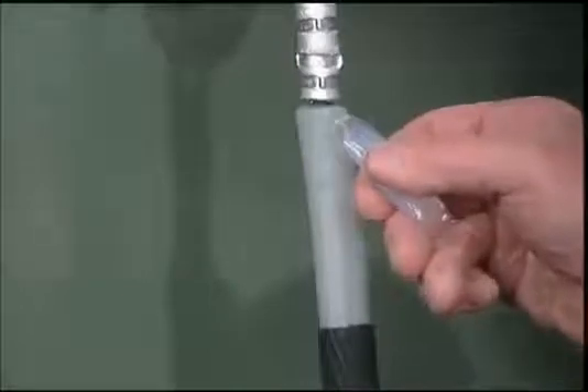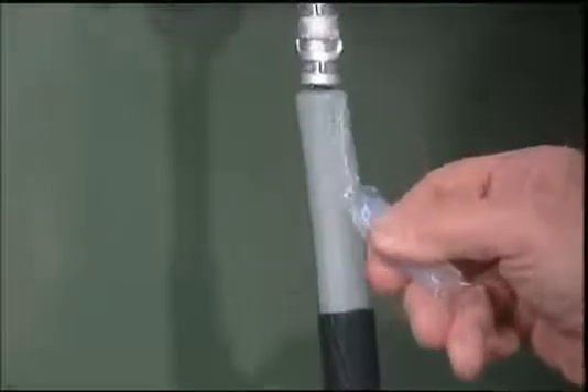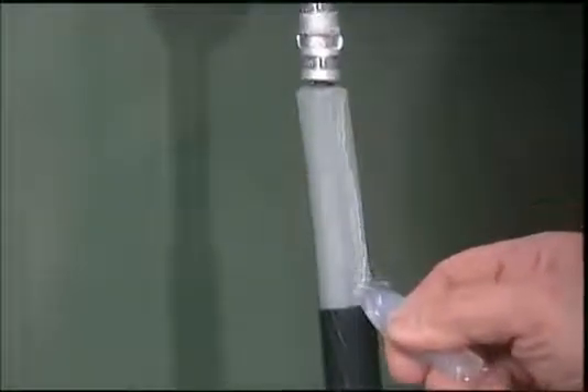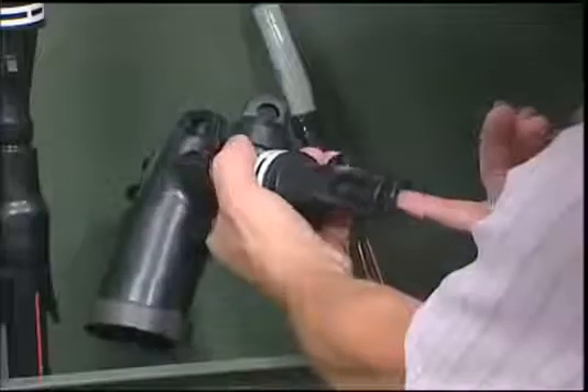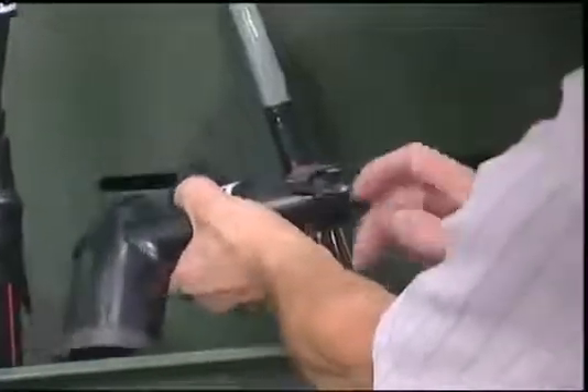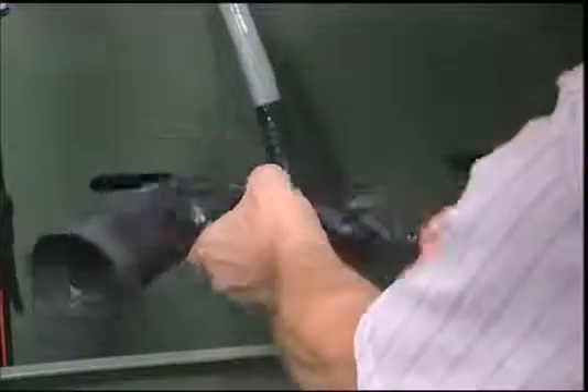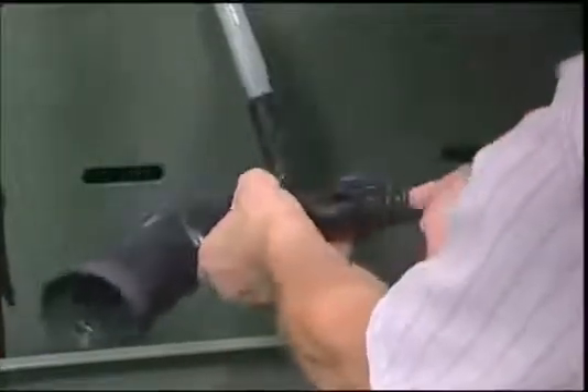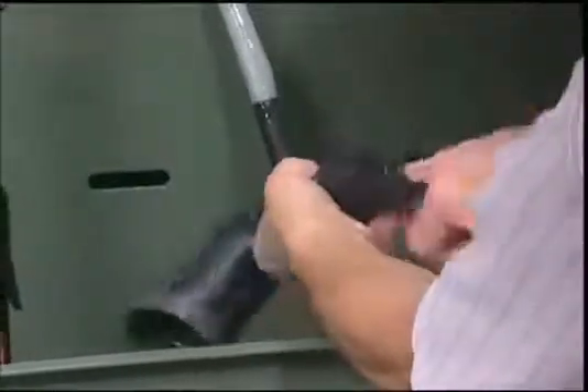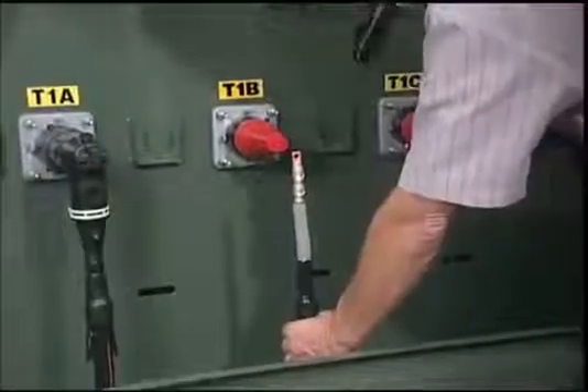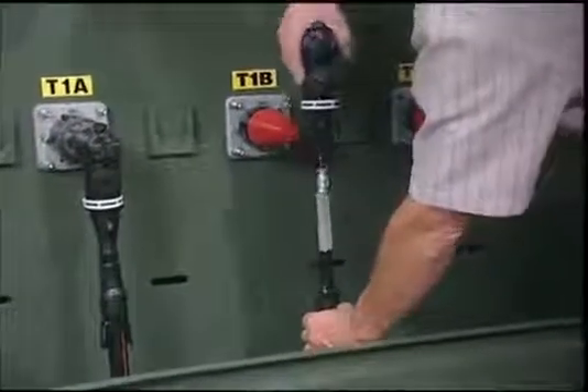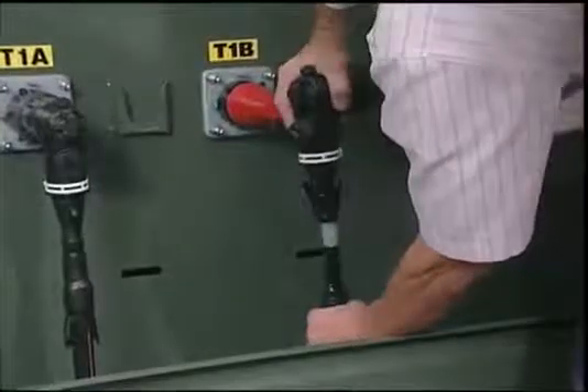Apply a thin, evenly distributed layer of the supplied silicone grease over the cable insulation and approximately 1/2 inch of the cable insulation shield. Apply a thin, evenly distributed layer of the supplied silicone grease as far as you can reach inside the elbow cable entrance. Now, push the elbow onto the cable. A slight twisting motion will help.